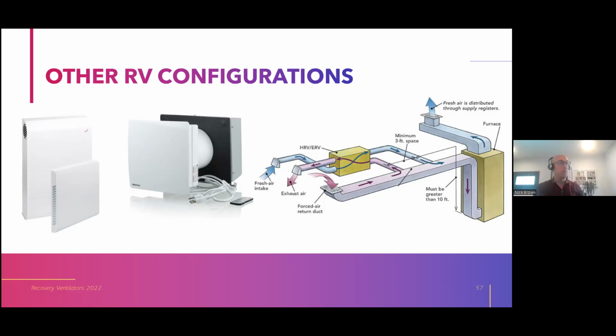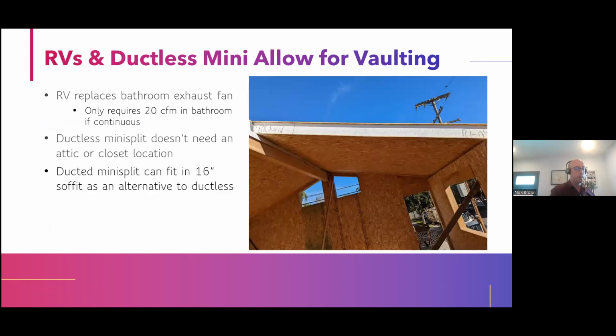I don't think that's optimal though, because it means your HVAC system has to turn on its main fan if you duct into the supply. It means your duct system really isn't optimized for the level of airflow of your recovery ventilator. And those are main problems because you don't know where that supply air and stale air is going to come from if your duct system isn't designed right. So I put it up there as an option, but it's one to be used carefully.